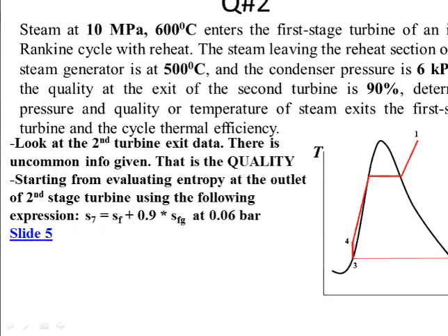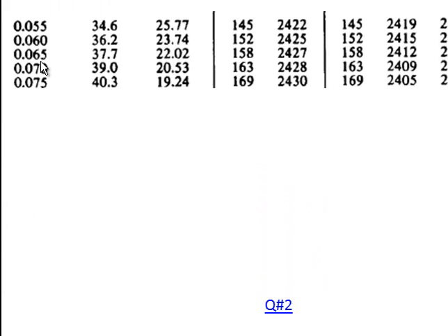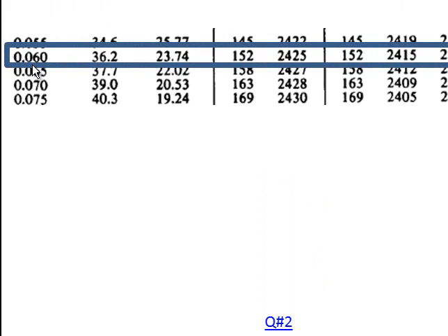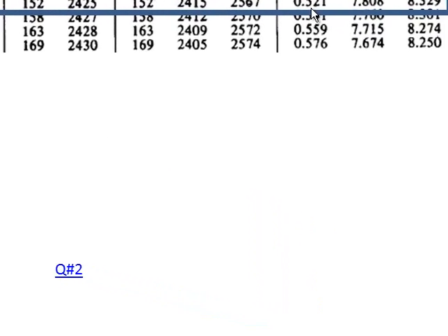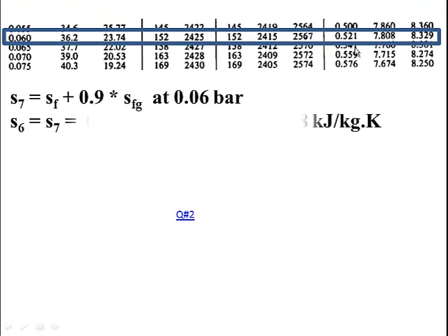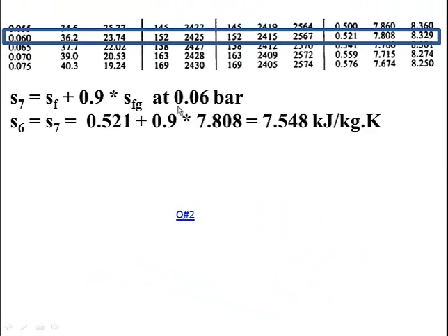We can find the entropy of state 7 using the expression s = s_f + x·s_fg. Going to the saturated steam table at pressure 0.06 bar, we find s_f and s_fg. Substituting the numerical values, we calculate the entropy of state 7, which is the exit from the second stage turbine.